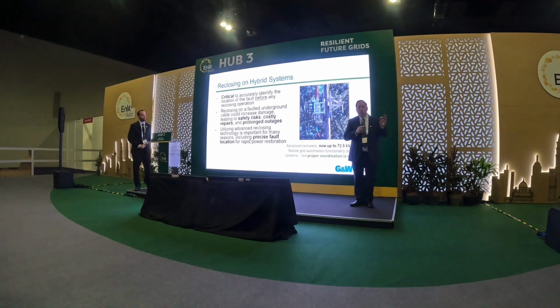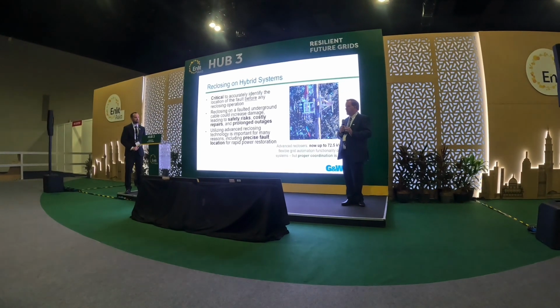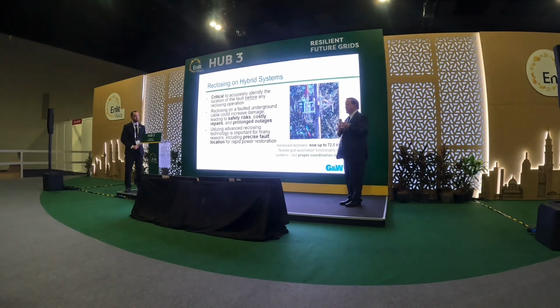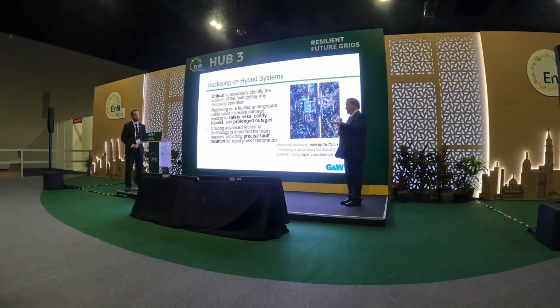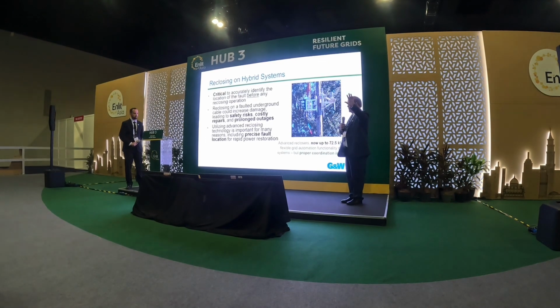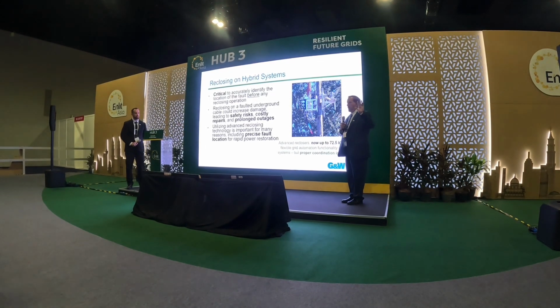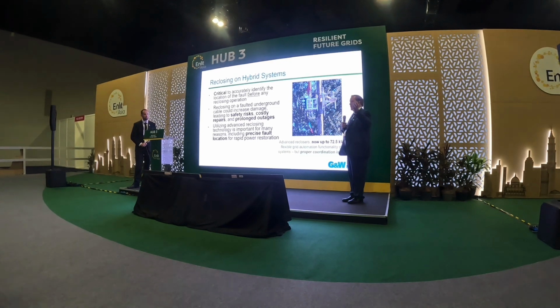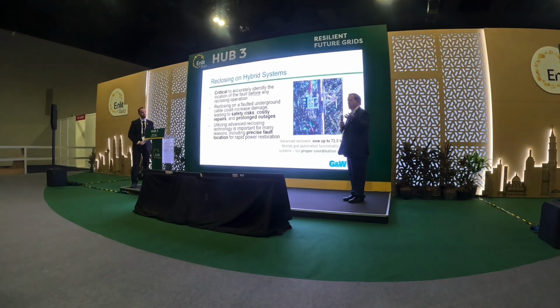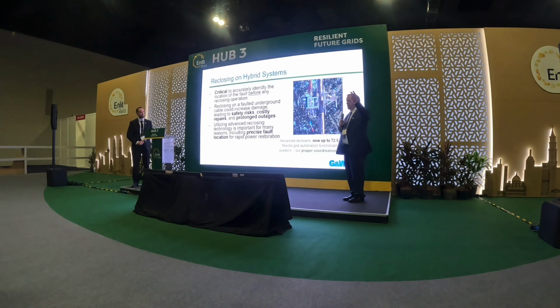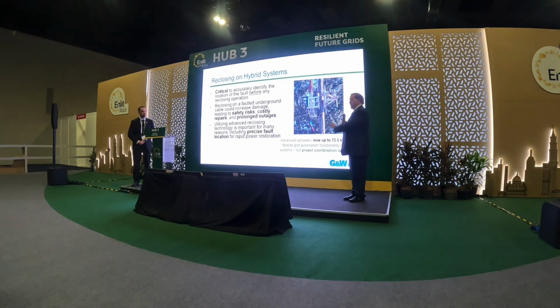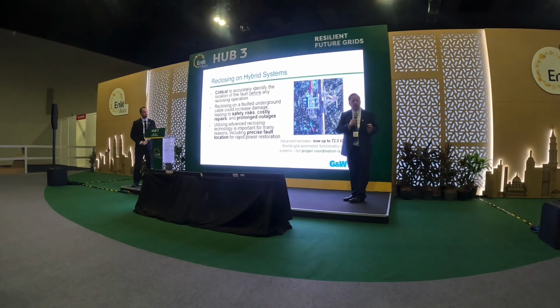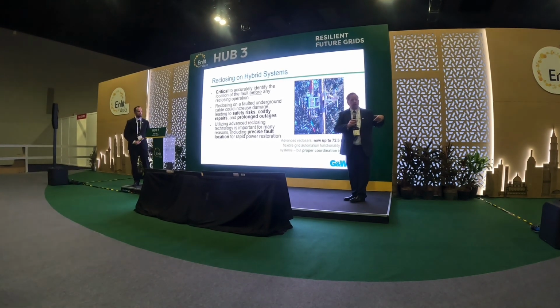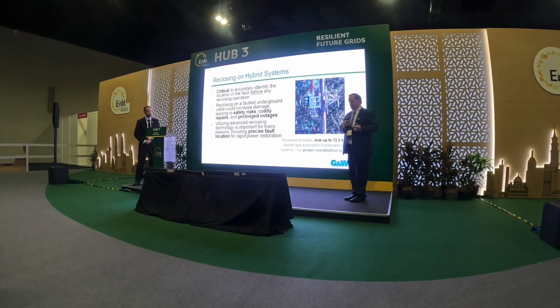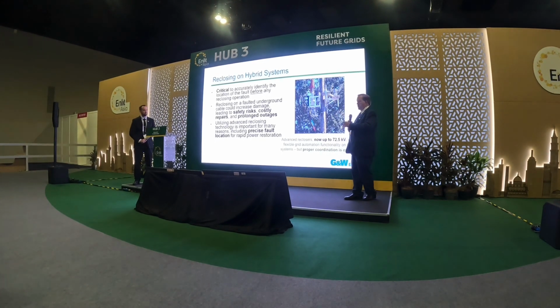And this becomes even more important when you look at the fact that technology is increasing so that there are now reclosers available up to 72 kV. These are sub-transmission levels. Obviously, if you have a recloser with, let's say, 31,000 amps of fault current at 72 kV, that is a huge amount of energy. If you have a hybrid system and that happens to be a permanent fault, that amount of energy, if you reclose in on that line, can be extremely devastating. It could be a huge safety risk, etc. So we'll talk about that.